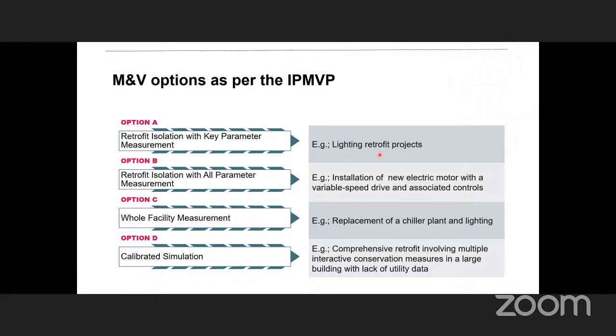Now, Option C, which is a very popular method, is to basically look at the whole building - looking at the utility bills and comparing the old utility bills to the new utility bills, plus the adjustments, obviously. That normally happens when you have a multitude of different energy conservation measures. Then Option C becomes probably a better option than Option A or Option B. You'd normally use it if the reduction expected is more than 10% of the whole facility consumption - below that, it will be very hard to quantify the savings.